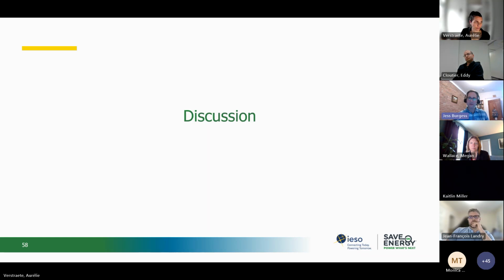Thanks, Jean-François. We had a question come in from Arda, and I think this was something that you presented on a few moments ago, Aurélie, asking for a little bit more detail on the anti-freeze alarms and their potential effect in the system. Yeah, you want an antifreeze regulation because if you don't have it, you may get ice on your heat exchanger and then you completely lose the efficiency of your heat recovery system. So sometimes you have a low limit in your exhaust line, and you may want to use your bypass damper just to make sure that you don't go under that low limit.